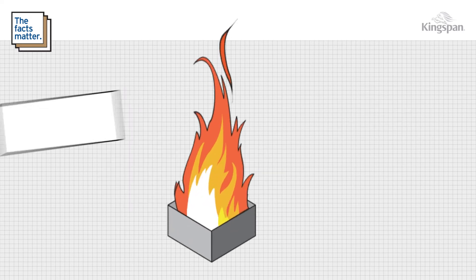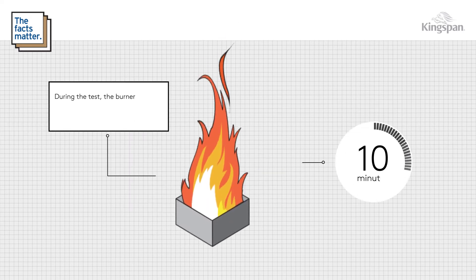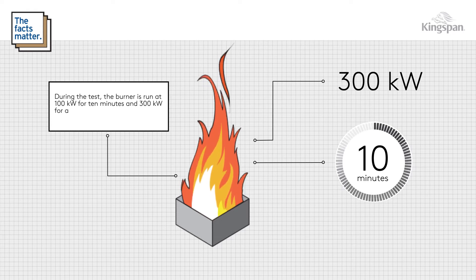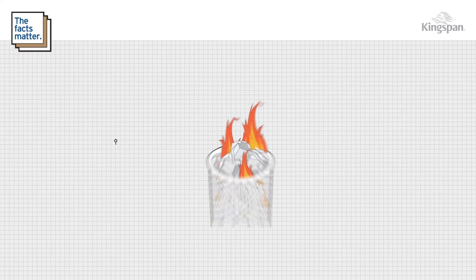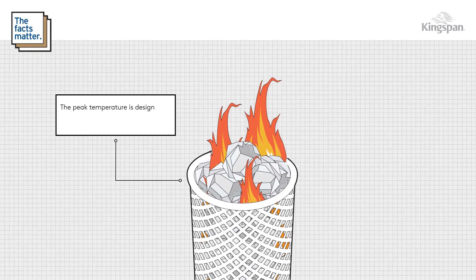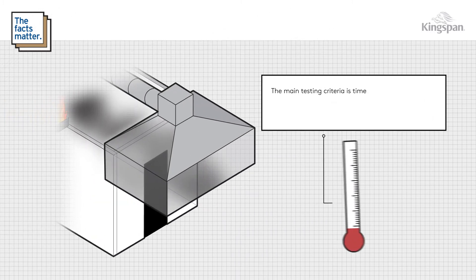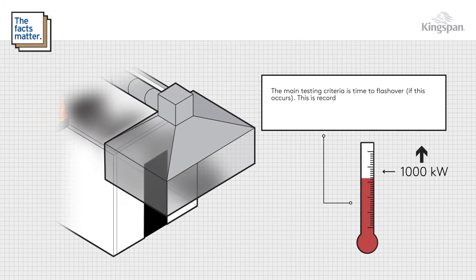A large exhaust hood is mounted outside the room above the doorway to capture smoke and gases exiting the room during the test. The burner is run at 100 kilowatts for 10 minutes and 300 kilowatts for a further 10 minutes, or until the room reaches flashover. The peak temperature is designed to approximate the heat output from a fire in a large waste paper bin.